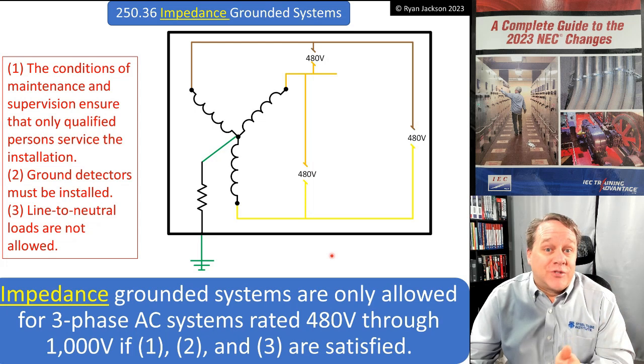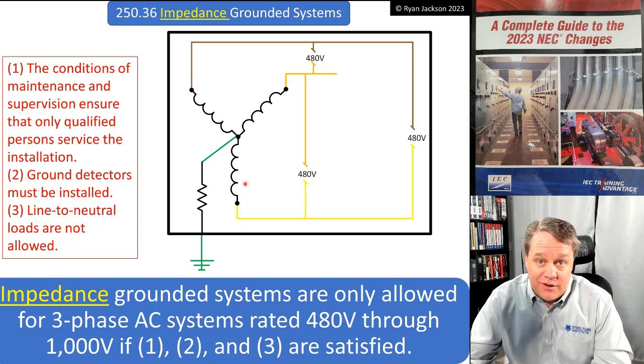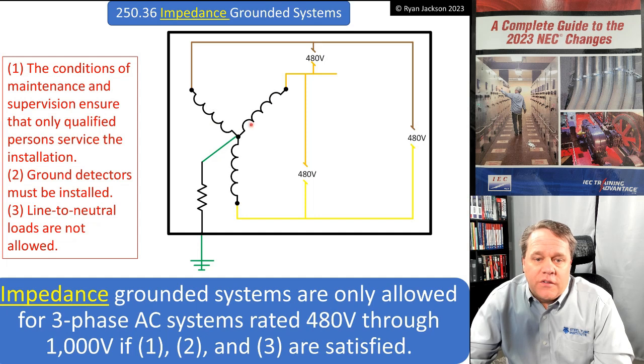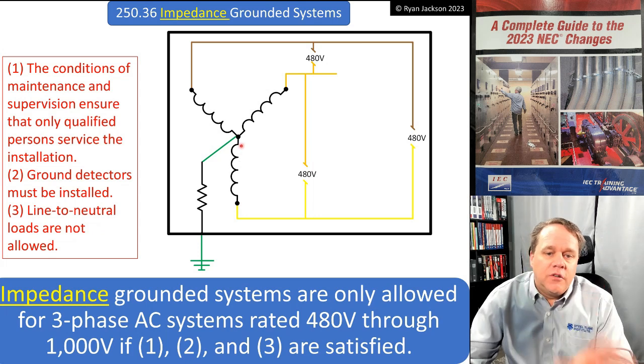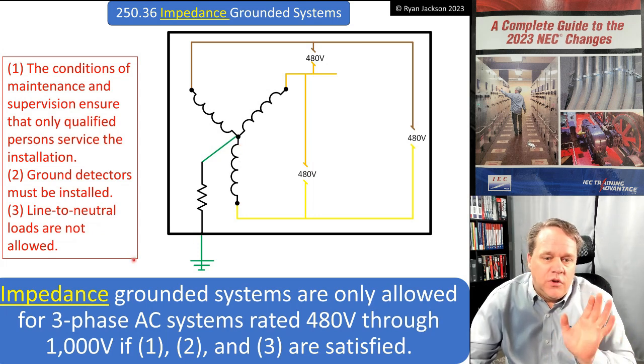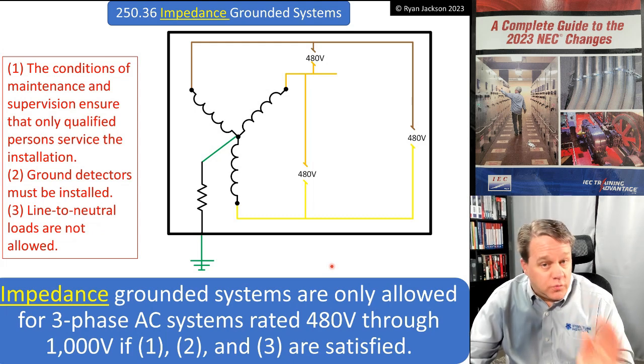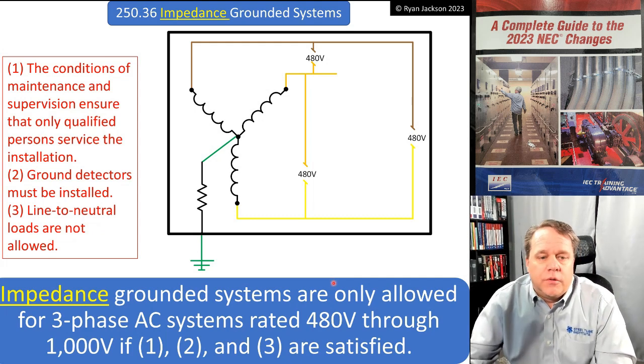An impedance grounded system is a Y-connected system - it's almost always going to be 480 volts or higher voltage. It is a Y-connected system and it does not have a neutral conductor. Section 250.36 says you can use an impedance grounded system for three-phase systems rated 480 volts through 1000 volts or more, as long as conditions one, two, and three are complied with.